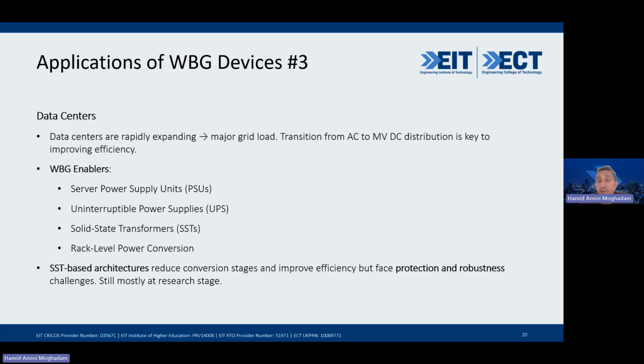That's where power electronics and wide bandgap devices come in. What they want to do is transition from AC to medium voltage DC to improve efficiency. Wide bandgap devices enable more efficient, compact server power supply units that support higher power densities and reduce energy loss. This allows for more servers per rack and lower total energy consumption.